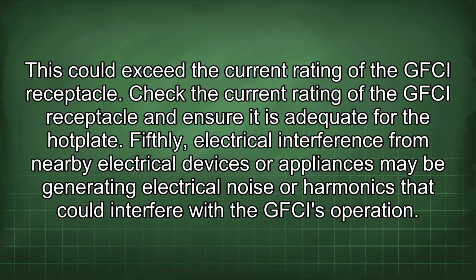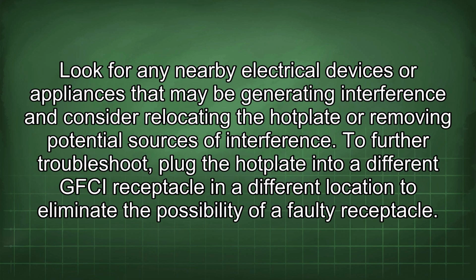Fifthly, electrical interference from nearby electrical devices or appliances may be generating electrical noise or harmonics that could interfere with the GFCI's operation. Look for any nearby electrical devices or appliances that may be generating interference and consider relocating the hot plate or removing potential sources of interference.